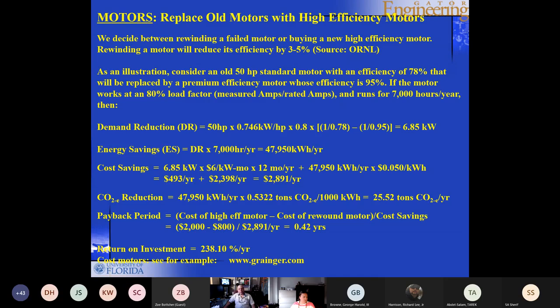You'll end up with $2,891 per year of savings. And the CO2 reduction corresponding to it, again, multiply by 0.5322, you get 25.52 tons of CO2 per year. Now, if you compute the payback, you get the cost of the high efficiency motor minus the cost of the rewound motor divided by the cost savings, and you'll end up with 0.42 years. And the return on the investment, you get the reciprocal of 0.42 multiplied by 100.